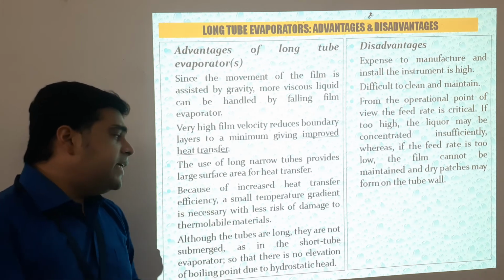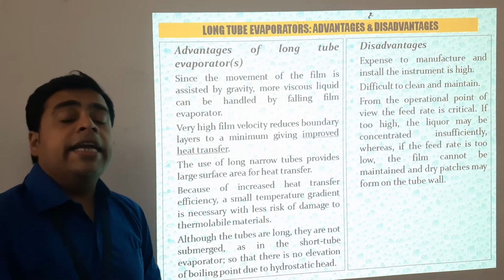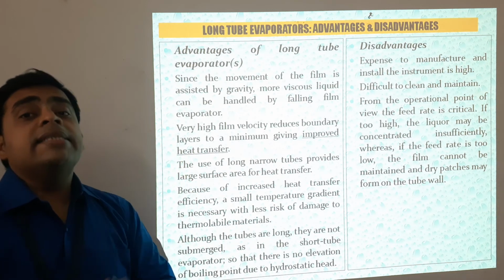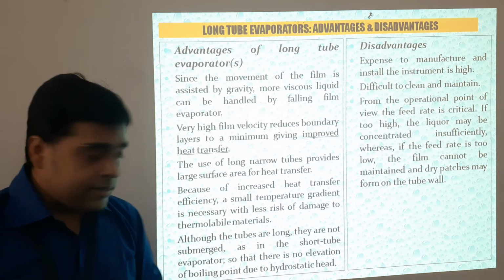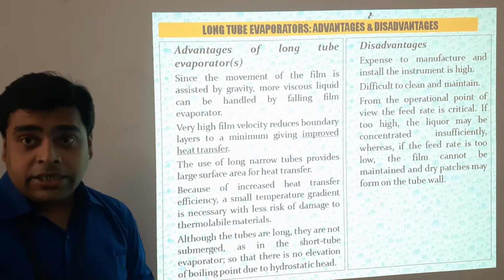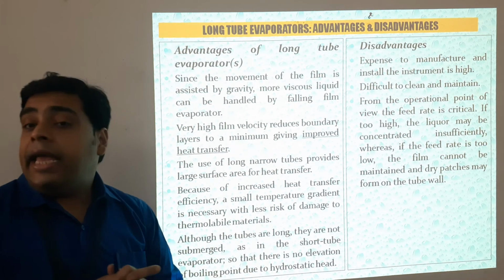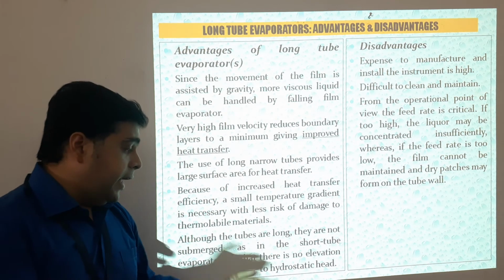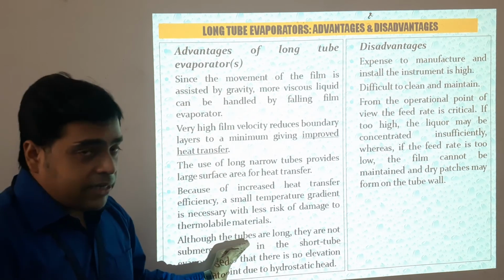Because of the increased heat transfer efficiency, a small temperature gradient is necessary with less risk of damage to thermolabile materials. And although the tubes are long, they are not submerged as in the case of the short tube evaporator, so that there is no elevation of boiling point due to the hydrostatic head. So these are quite advantageous.